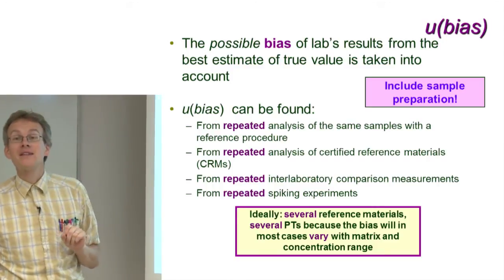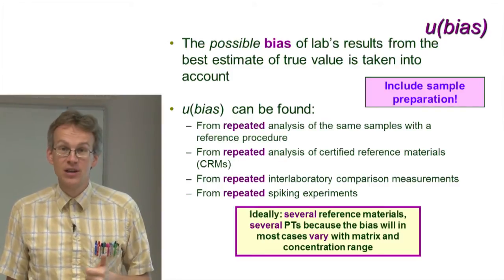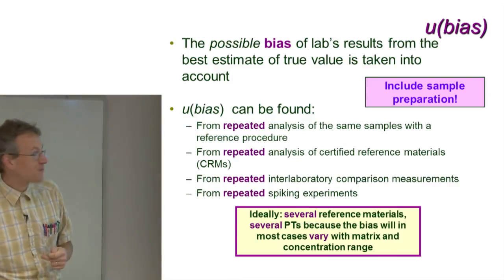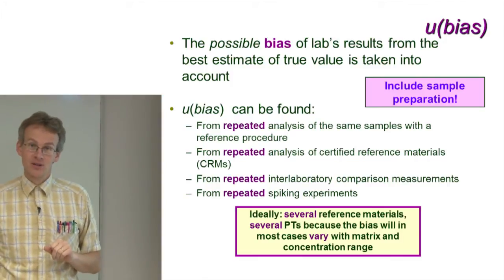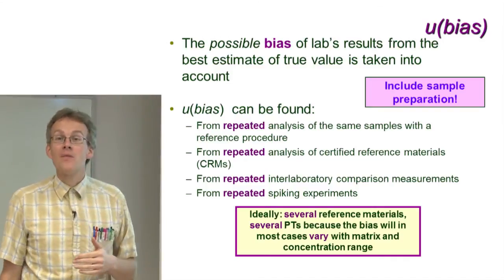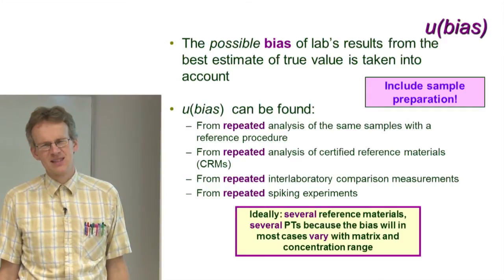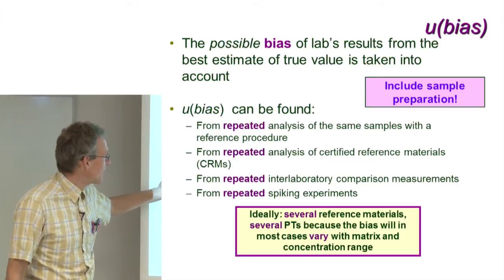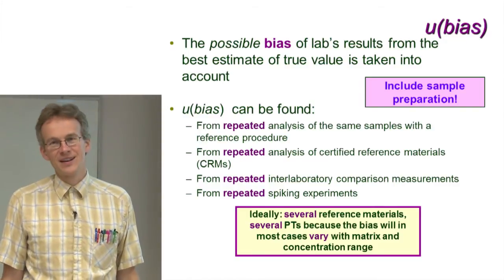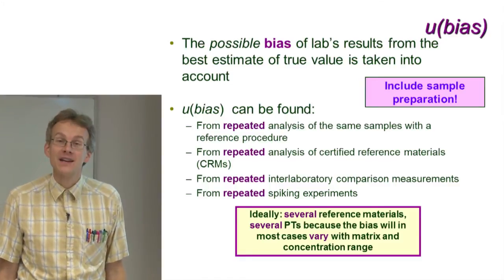The next possibility is to participate in interlaboratory comparison measurements. In interlaboratory comparisons, the organizer eventually announces the so-called consensus or reference value, so that you will have a reference value for your sample. Unfortunately, in most cases — and in almost all cases of proficiency testing — the reference values are found from the results of the participants. Since there are always participants of quite different levels, these consensus values cannot be called very reliable, and when used for bias estimation, overestimated bias is often the result.